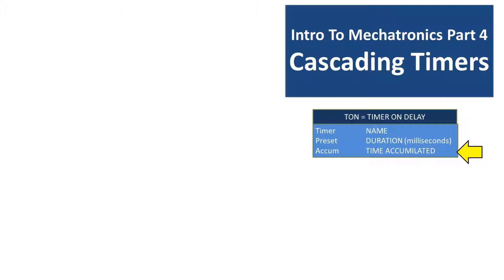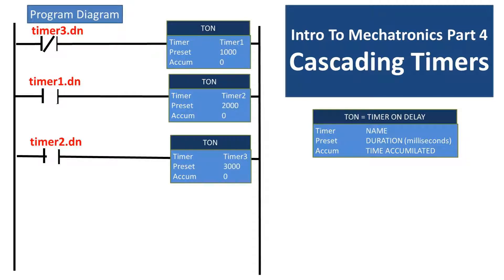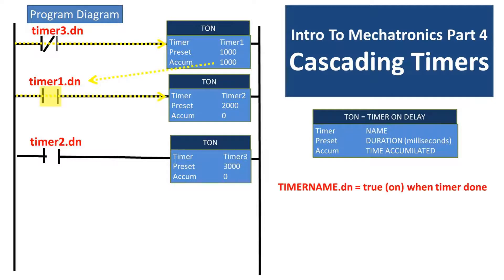Once this value reaches the duration value, the timer reports a true or on state. To the left, I have a program ladder diagram that has cascading timers on it, or timers that go off one after the other. I put a normally closed connection at the beginning, which will start the program off, and timer1 will run for one second, or 1000 milliseconds. To start the next timer, we'll be using timer1.done, which is true or on when the timer is done. After timer1 is done, this will activate the second rung, normally open contact, connecting it and starting timer2 up until it goes to the accumulated value of 2 seconds.